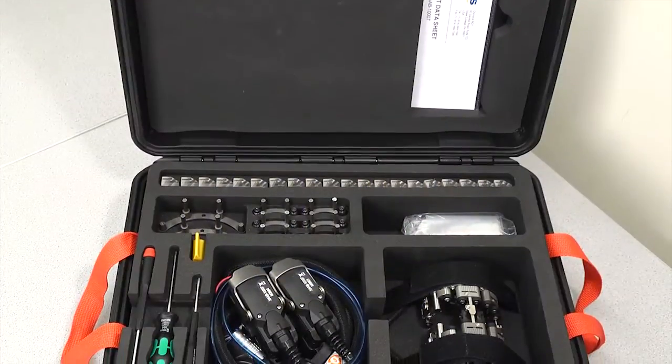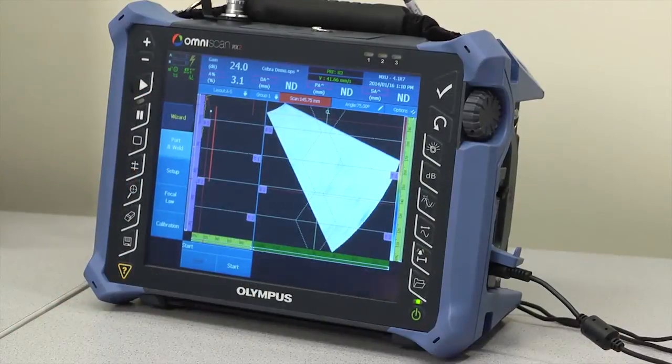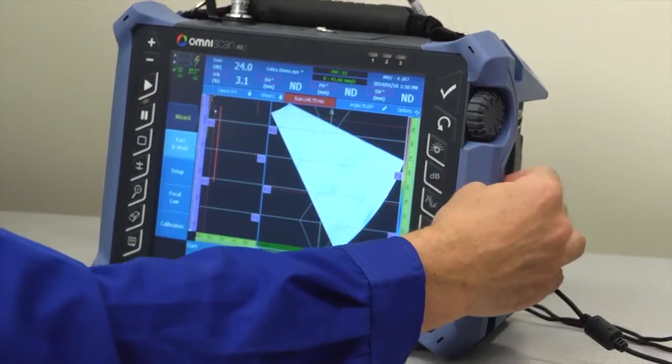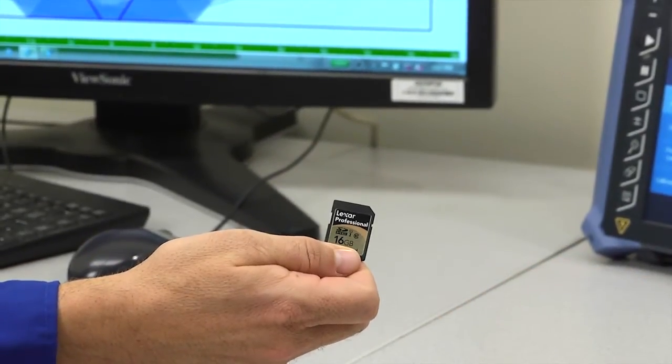Depending on the complexity and number of probes required, the inspection strategy and probe parameters can either be created directly on the OmniScan or imported from the SDHC memory card.